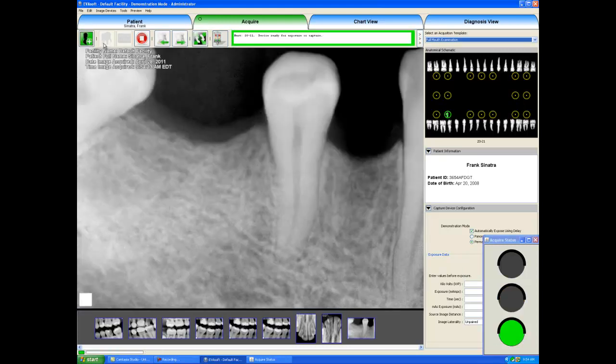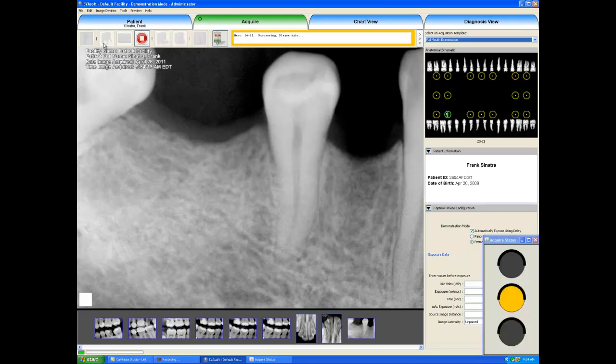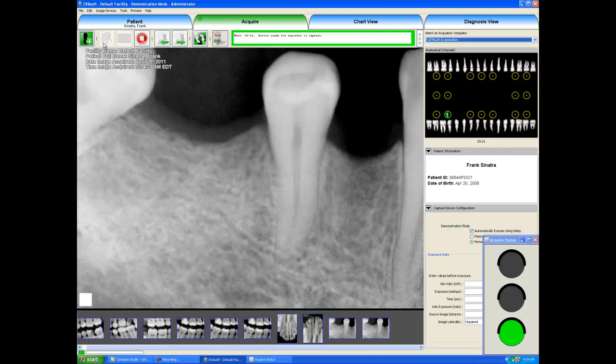The sensor will remain live. So you could just reposition it sometime later. Take the x-ray. And it will load again on the screen. It will continually load in that chart position for every time that you take an x-ray.